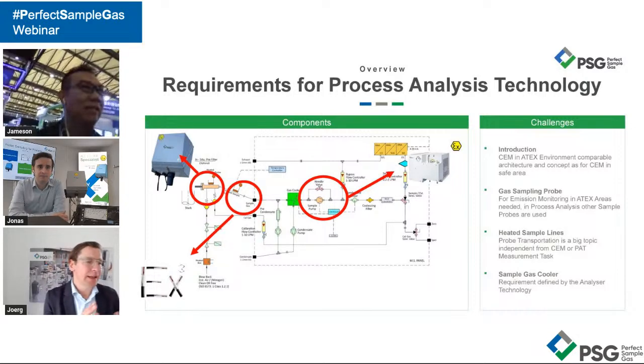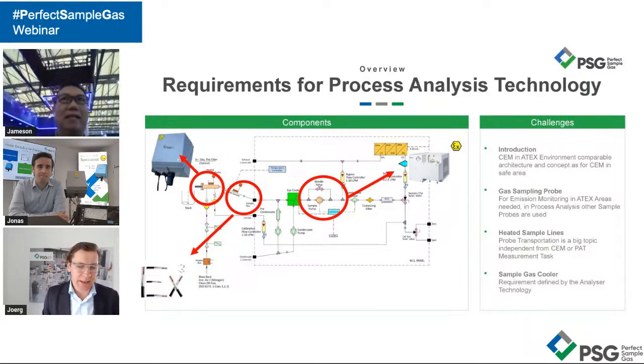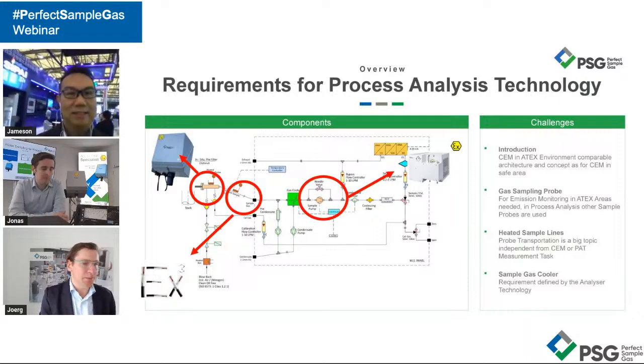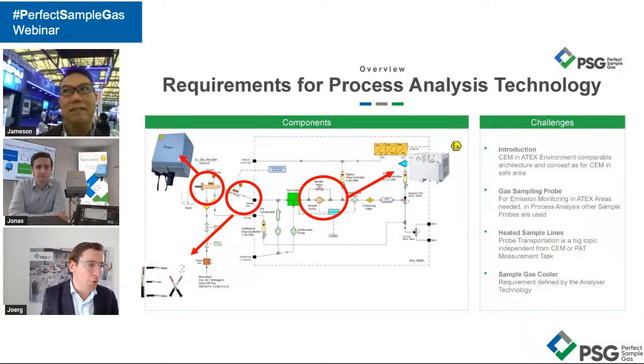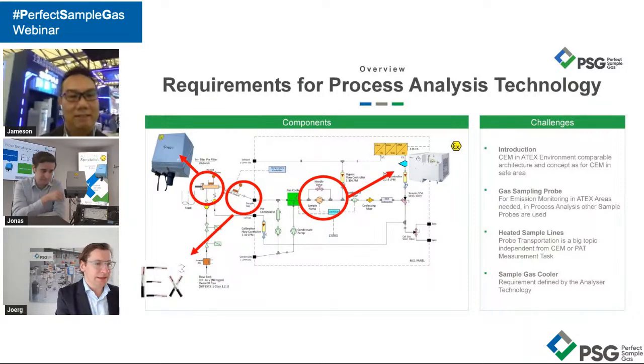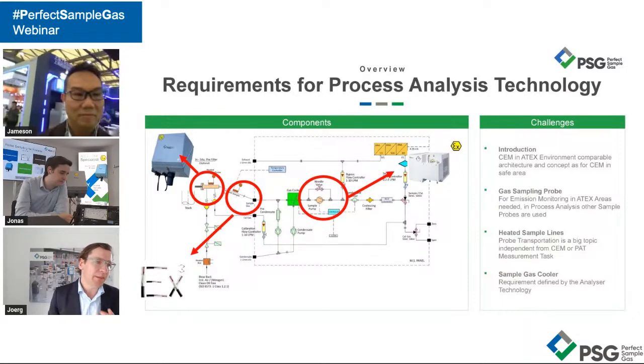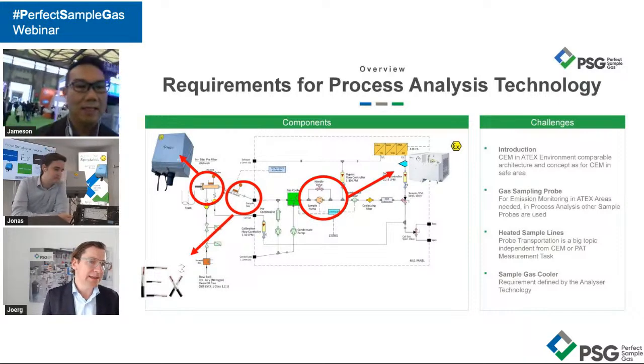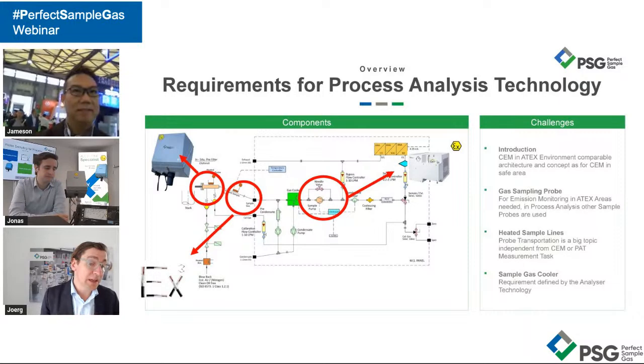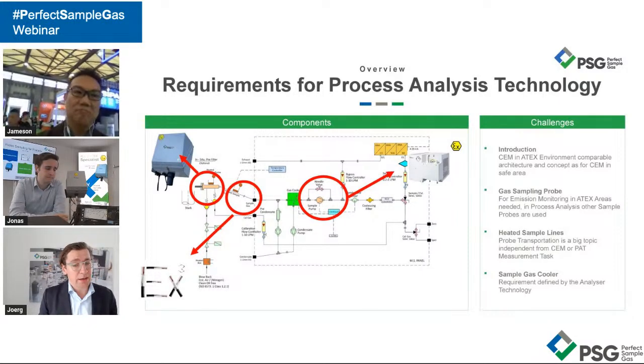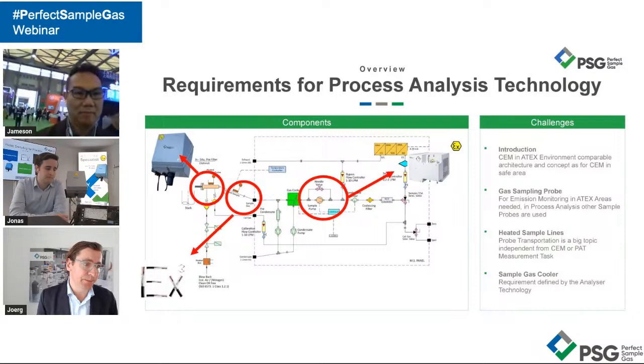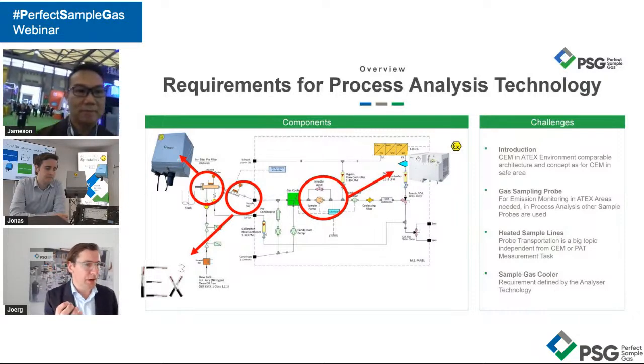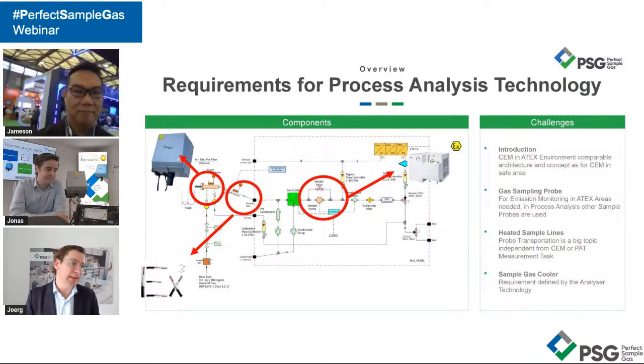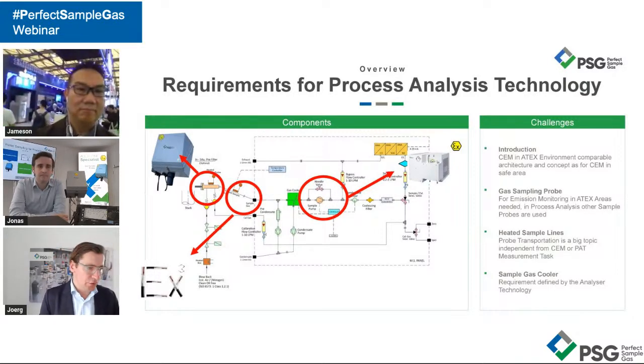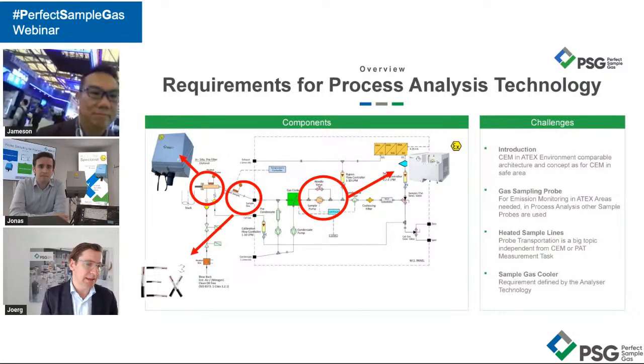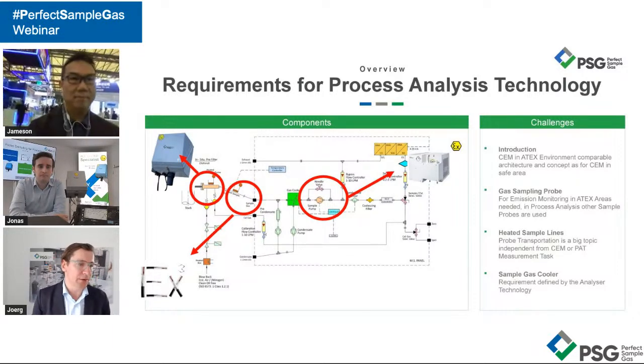I just wanted to say, a CEMS system in an ATEX environment has the same concept. We are sucking the gas sample through the probe, so filtration, for example, is a topic, and this is maybe a change to process analysis technology, to process monitoring, where maybe there's a positive pressure, so there's no gas sampling pump needed. Maybe there's also no cooler needed, depending on the analyzer, the analysis technology, right?